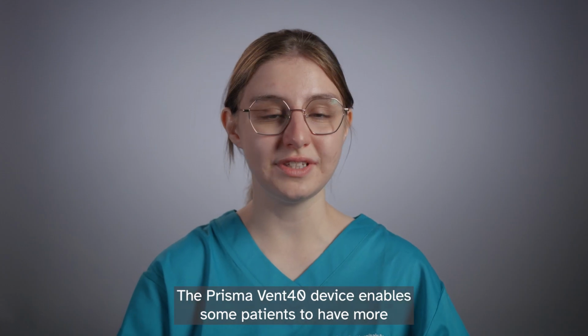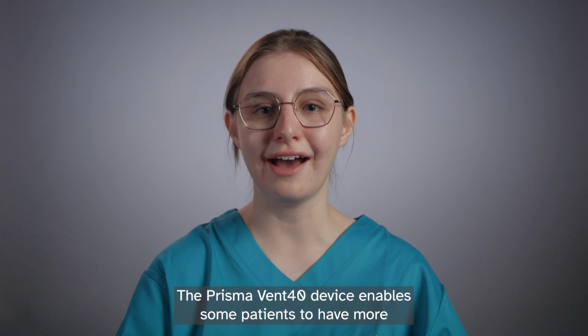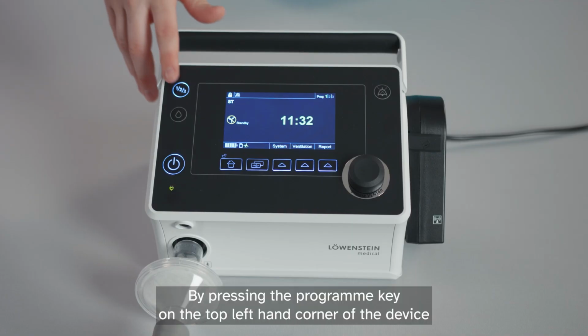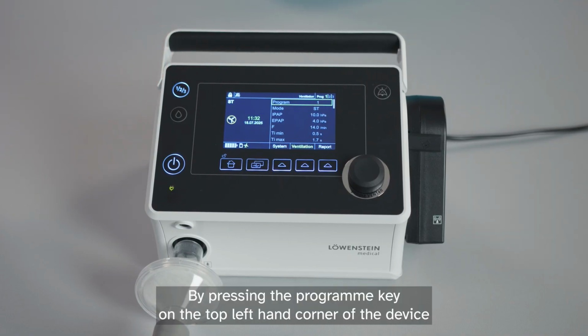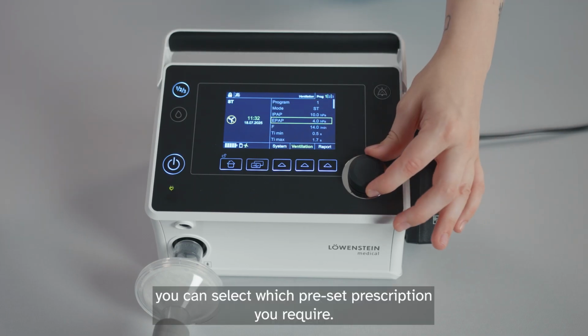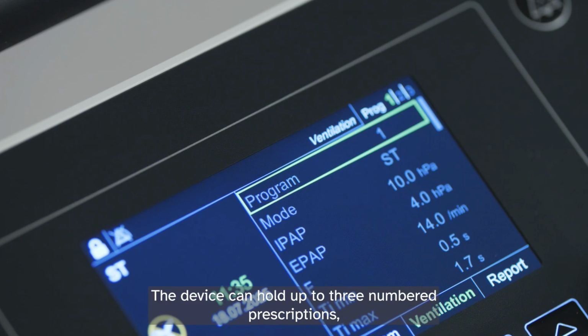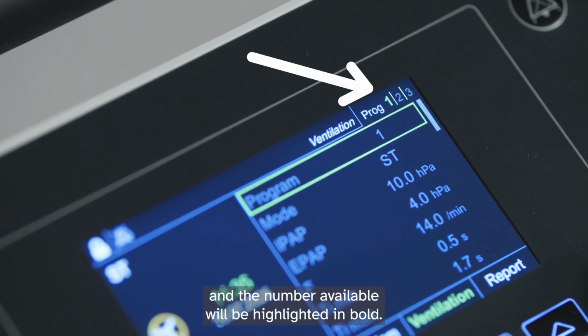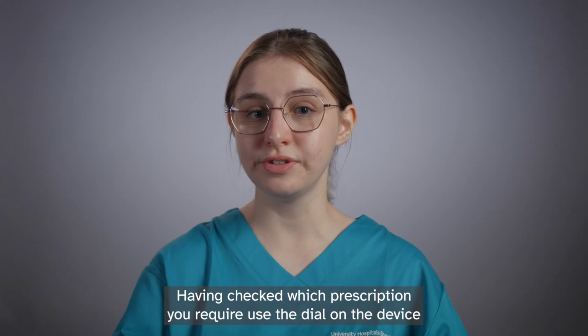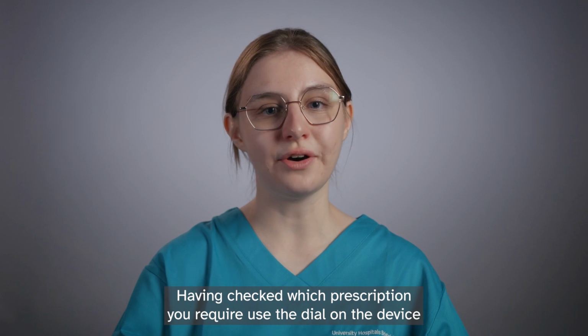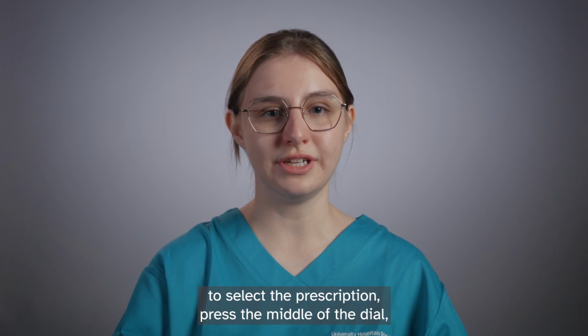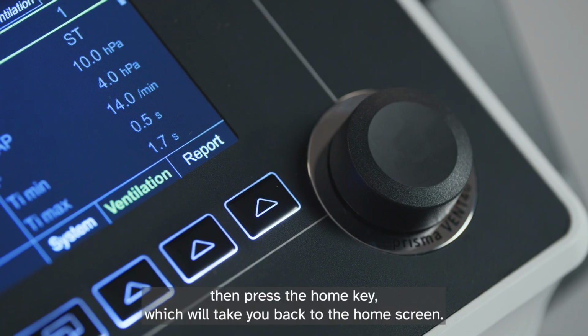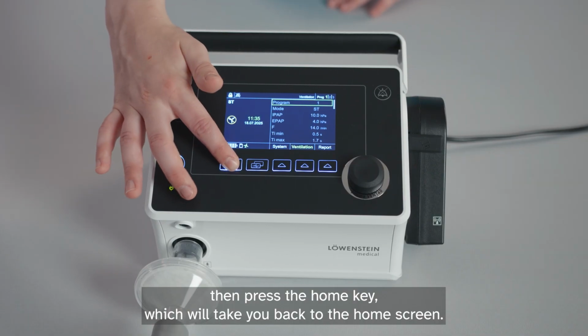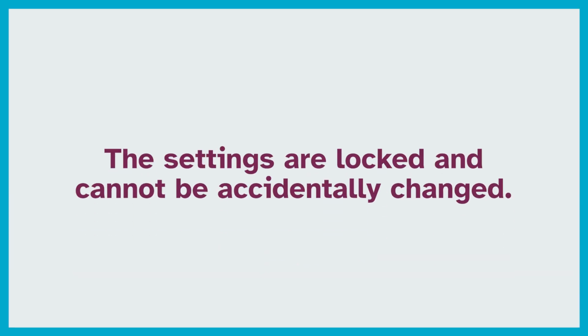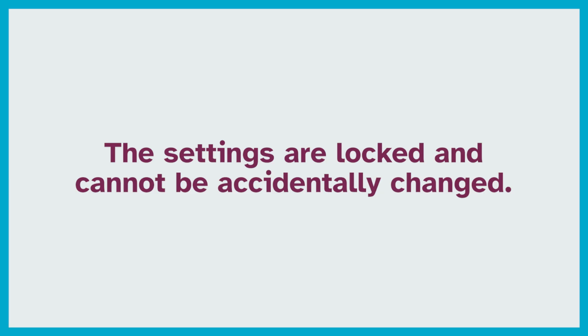The Prisma Vent 40 device enables some patients to have more than one prescription. By pressing the program key on the top left-hand corner of the device, you can select which preset prescription you require. The device can hold up to 3 numbered prescriptions, and the number available will be highlighted in bold. Having checked which prescription you require, use the dial on the device to select the prescription. Press the middle of the dial, then press the home key, which will take you back to the home screen. The settings are locked and cannot be accidentally changed.